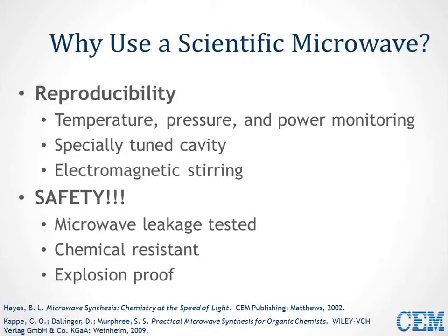Of course, in laboratories, teaching laboratories, safety is of the utmost importance, and these scientific microwave systems are designed with safety in mind. They've been tested for microwave leakage, and they're verified to be well below the limits of what you can have for microwave leakage. They're resistant to the chemicals.